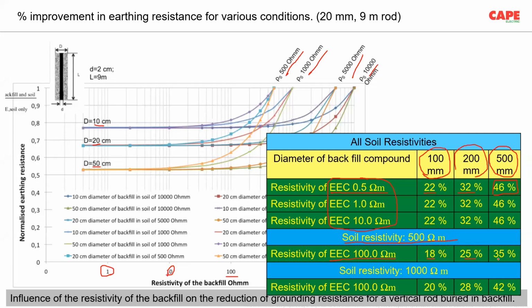200 mm filling 25%, 500 mm filling 35%. Soil resistivity of 1000 ohm meter, resistivity of the earth enhancing compound is 100 ohm meter, then the improvement is something like this. So basically, what I wanted to tell you is if you are filling 100 millimeter, why I stress this 100 millimeter again is, in most electrical installations, we take a hole of 4-inch, 100 mm, put a rod inside and fill this gap with the earth enhancing compound. So typically it is about 100 mm.